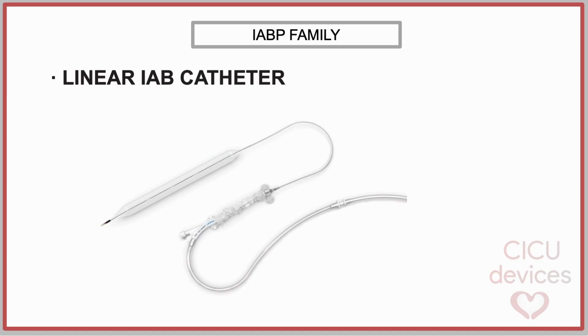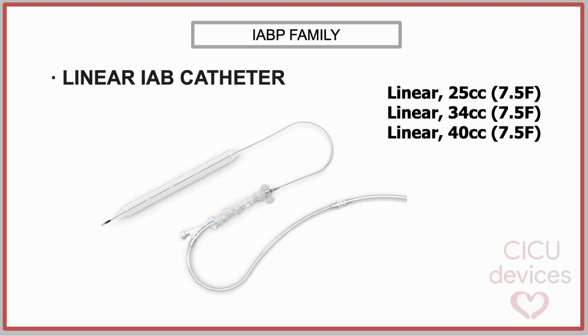The Linear fluid-filled IABP catheter is Getinge's standard intra-aortic balloon catheter designed for routine clinical use. It incorporates a conventional fluid-filled lumen for central aortic pressure monitoring. The catheter has an external diameter of 7.5 French, offering a balance between ease of insertion and effective hemodynamic support. The Linear catheter is available in 3 balloon volumes to accommodate different patient sizes: a 25 milliliters balloon for patients shorter than 152 centimeters, a 34 milliliters balloon for patients between 152 and 162 centimeters, and a 40 milliliters balloon for patients taller than 162 centimeters.